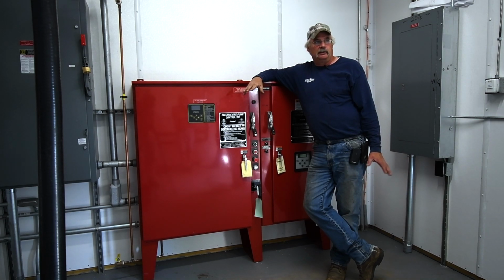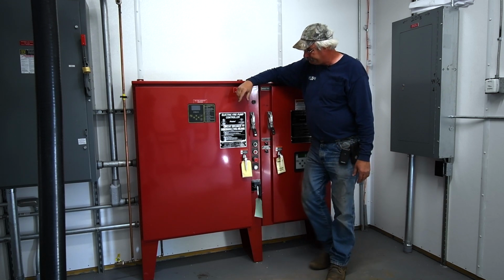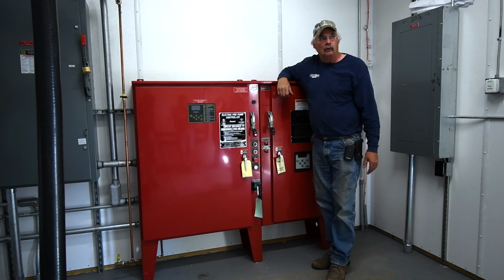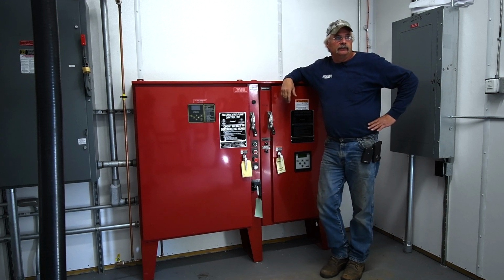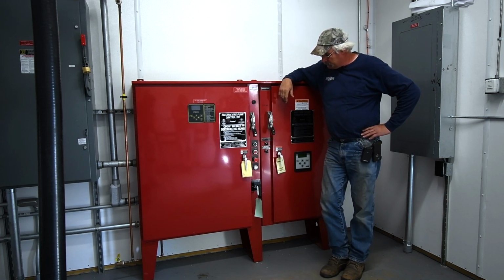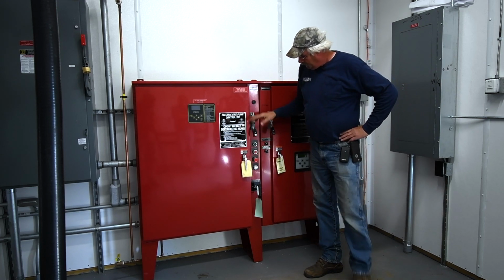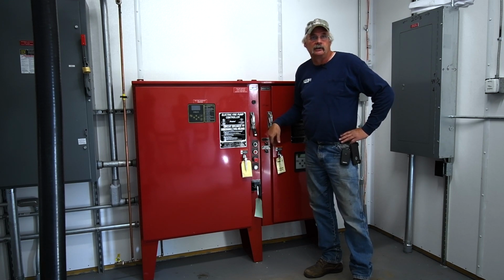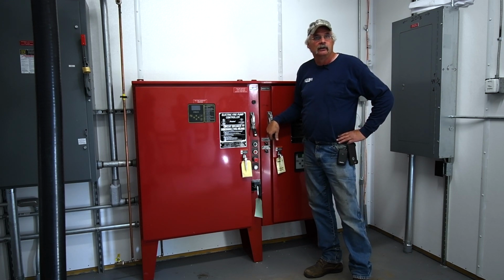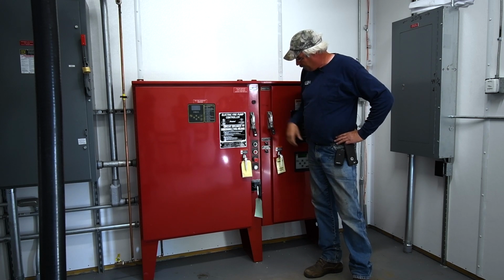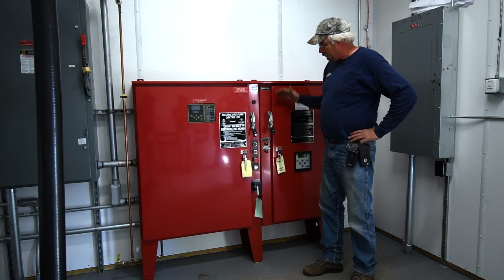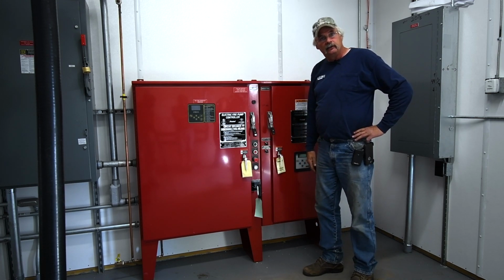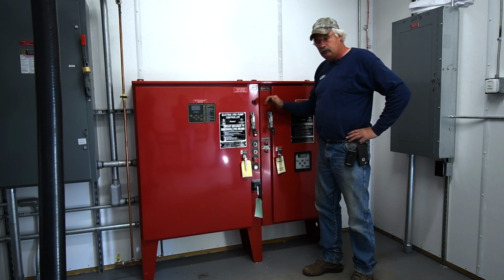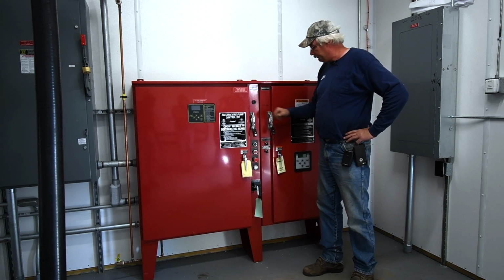All your pumps are set up on pressure. So once the pressure drops in the system, then your diesel, if you have a power outage, will actually turn on your fire pump. Basically, these two switches are off because the systems aren't monitored yet. Normally these two levers will be up. So if you go to shut any of this stuff off again, you have to contact Ben Bowstring with the school district to make sure that you're doing any work on any of the fire protection.